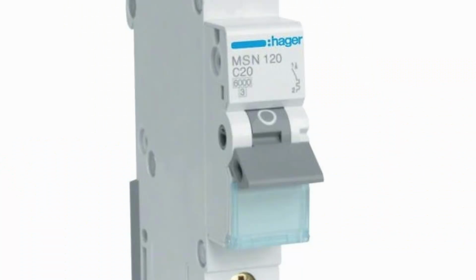Now, where you might run into strife is that the typical circuit breakers used in Australia for 10 amp power circuits is 20 amps.